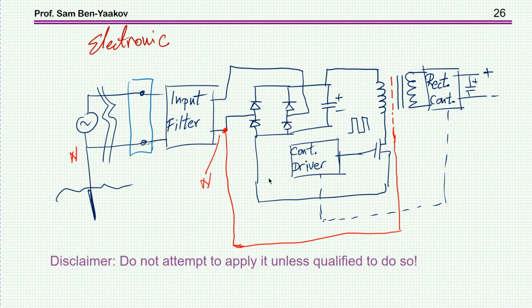Let's have a look at how you connect it. This is now the shield, and the place to connect it to would be the neutral. So here we have a sort of plane, a metal cover of the primary, which has the potential of the neutral. This is now the capacitance between the neutral and the secondary. So referred to ground, there's no potential here, or very low potential, and you won't feel anything when you touch the metal casing. This would be a way to remedy the problem.